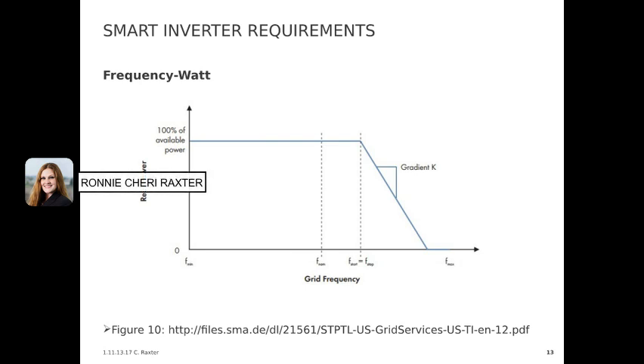The next functionality is frequency watt, also called FreqWatt. This functionality is actually optional. It's required to be activated when available. The reasoning is because not all DERs have the FreqWatt functionality. And to explain what the frequency watt function is, this specific functionality reduces the power output of the DER inverter if the grid frequency is high. The reason behind this is a high frequency event is an indication that a traditional generator is being underutilized and is spinning faster than it's intended. By reducing the power output of the DER, it'll increase what is being consumed from the generator and slow the spinning down to the point where the frequency is where it is intended to be. This stabilizes the utility grid and does not overtax the generators connected to the grid.